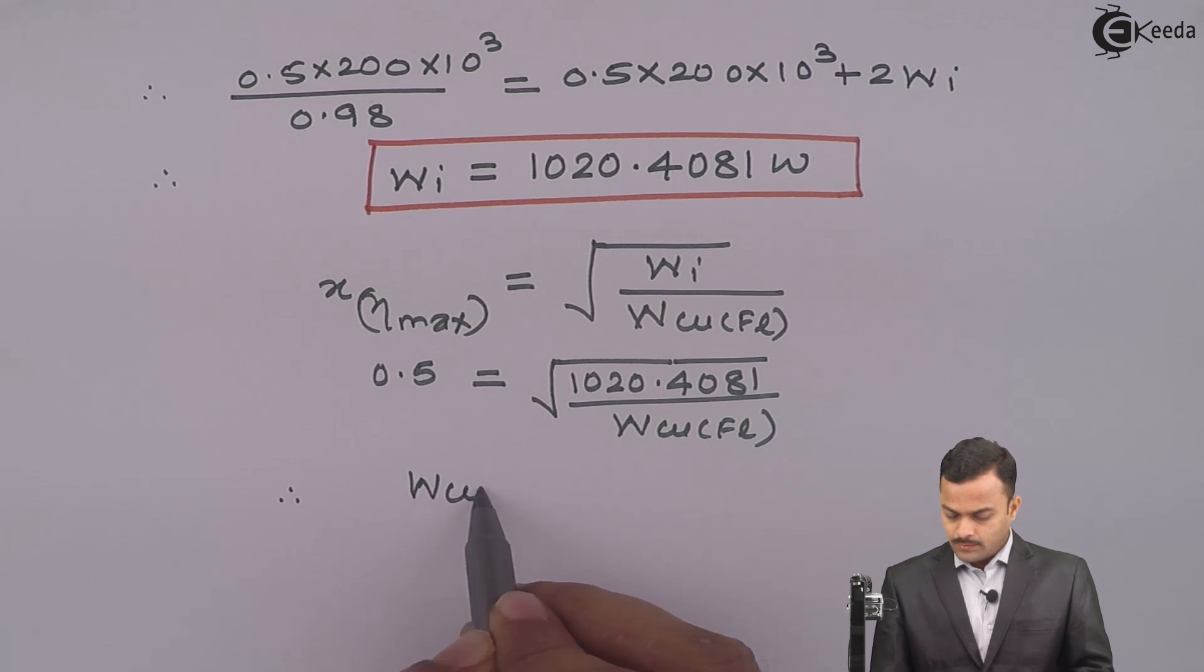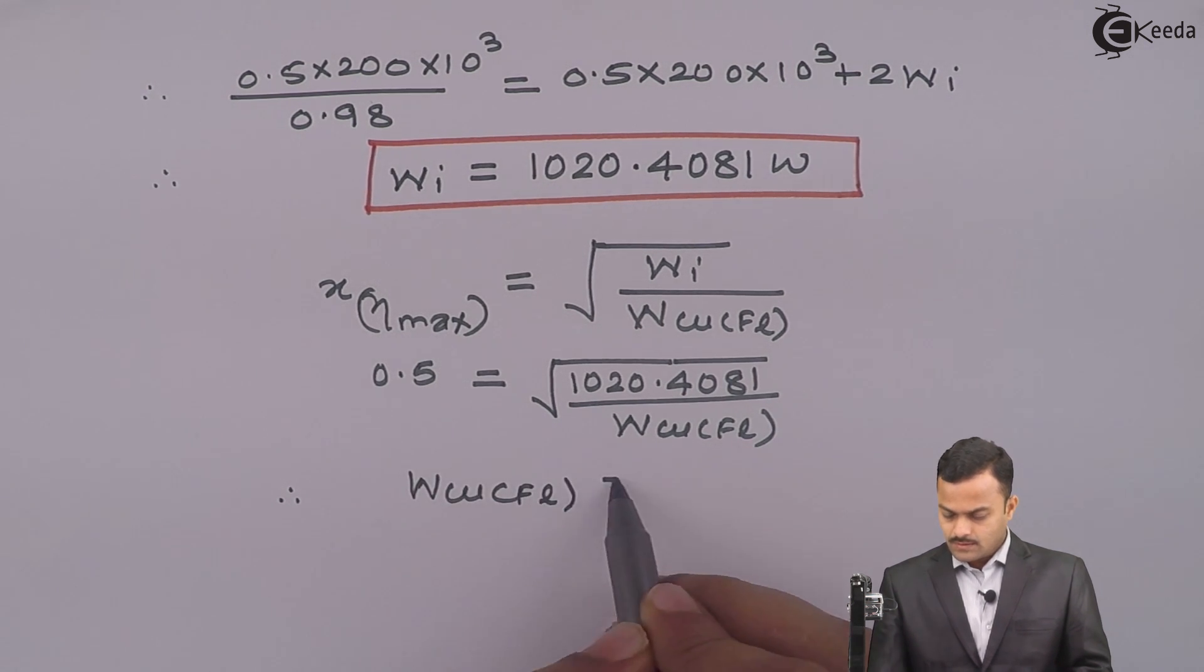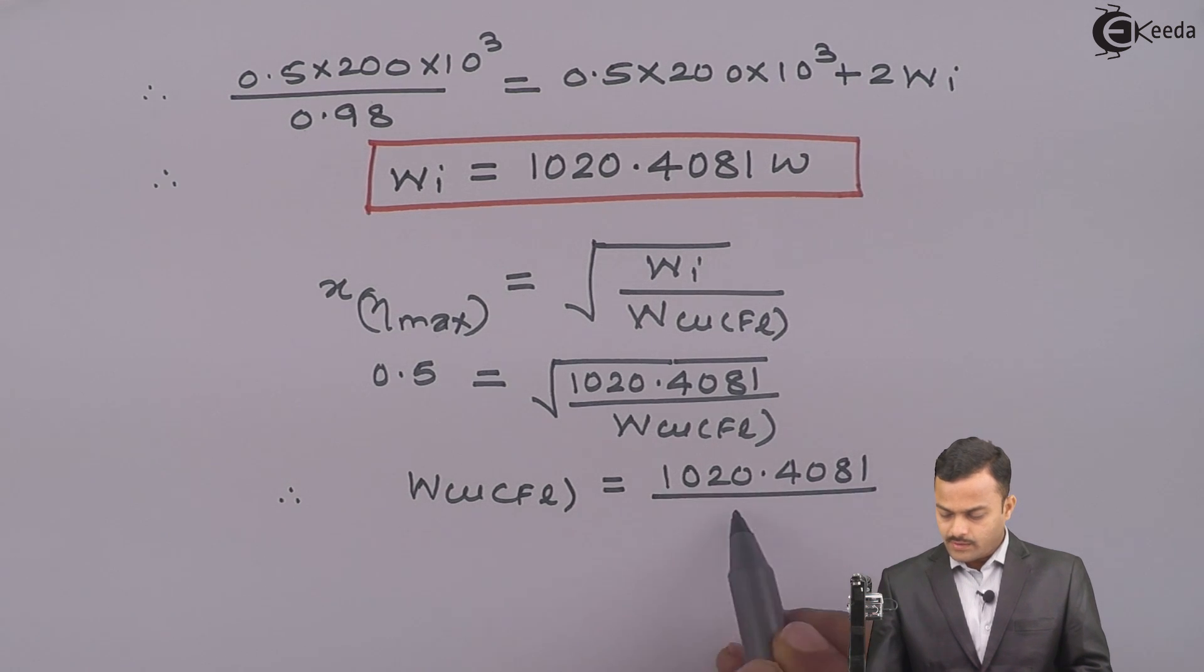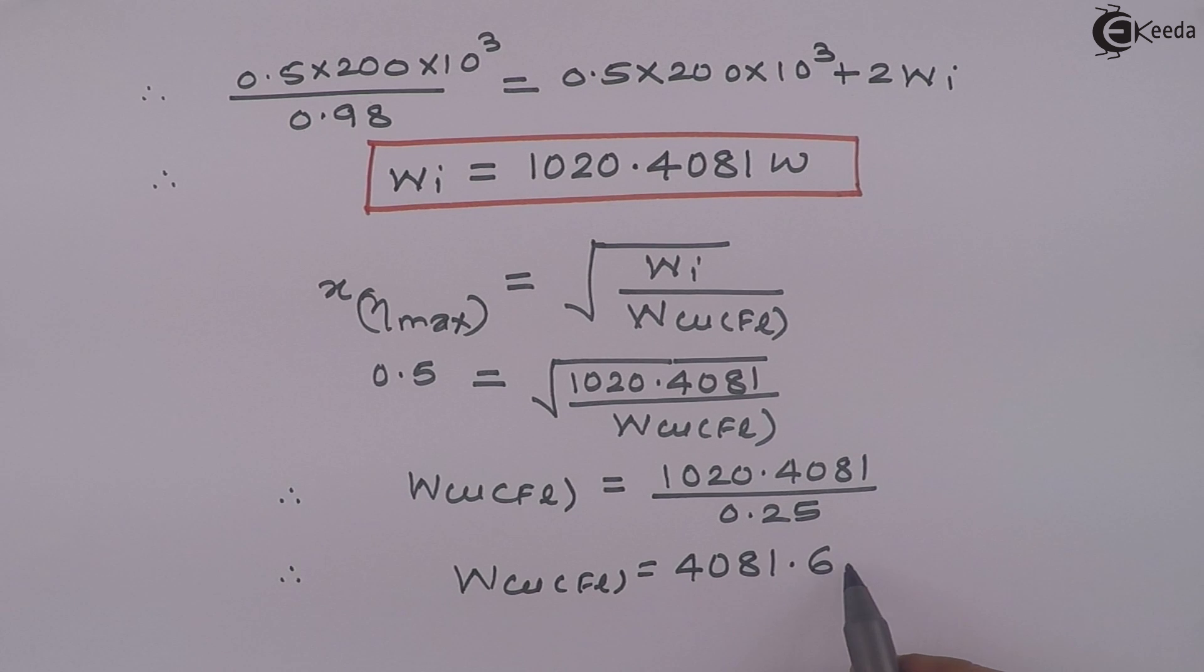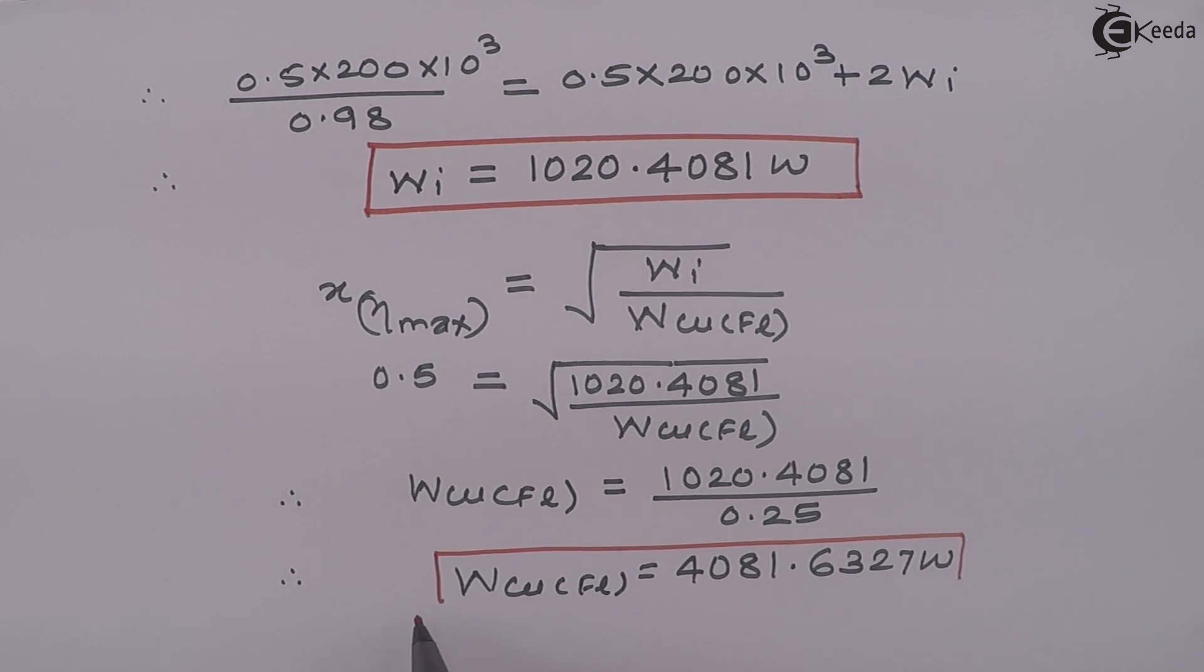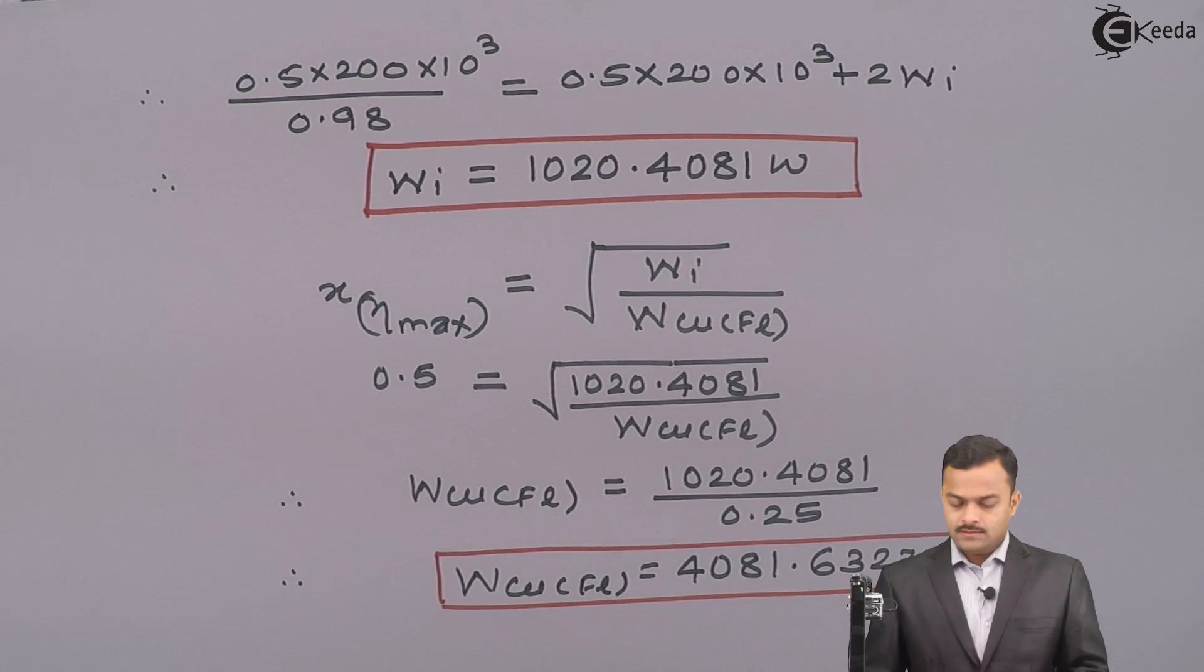So if you solve this, you will get WCUFL equal to 1020.4081 divided by 0.25. The answer you will get is 4081.6327 Watt. Full load copper loss we have calculated. This is very useful because we can get efficiency at any load.